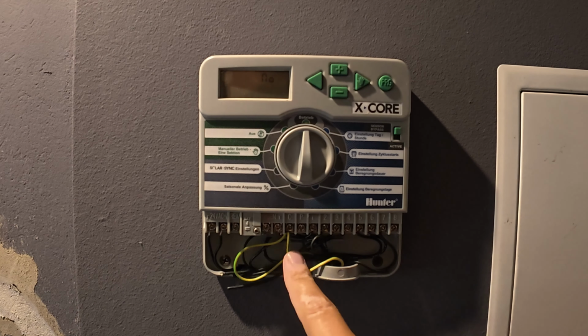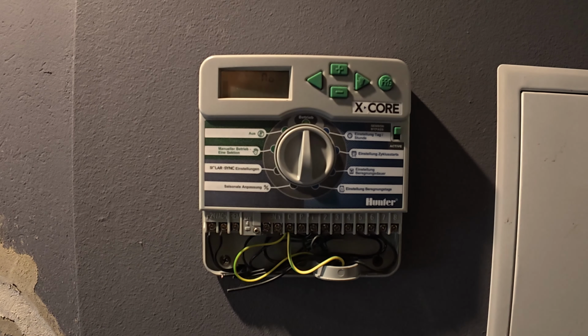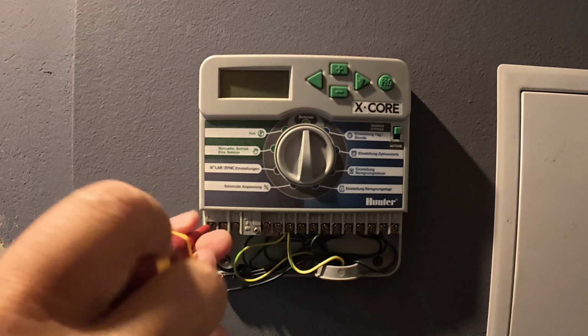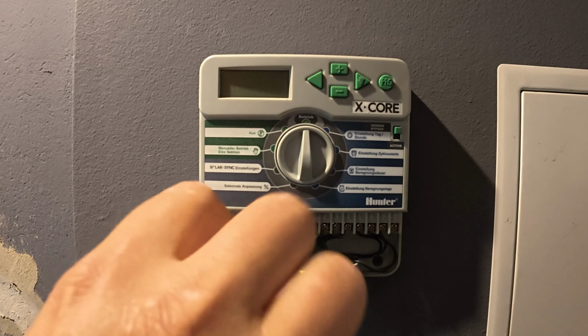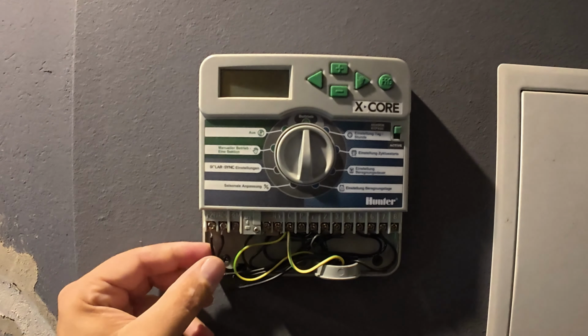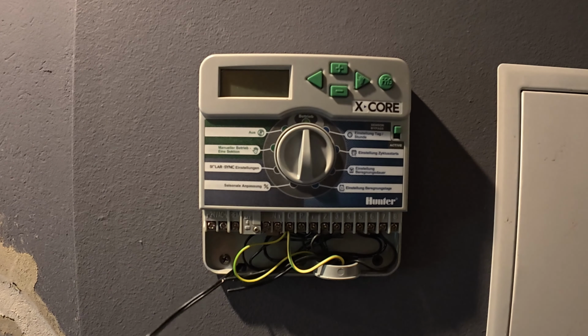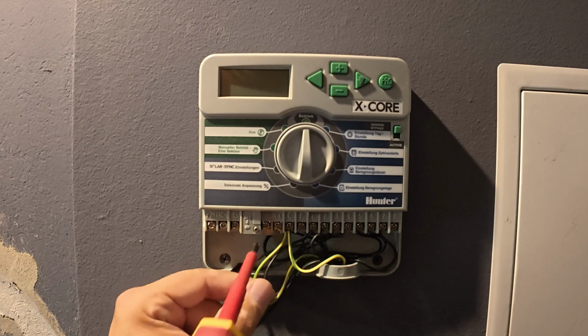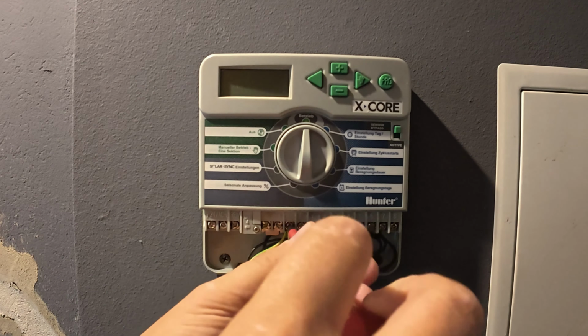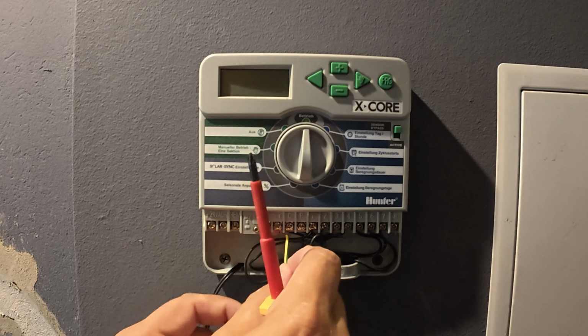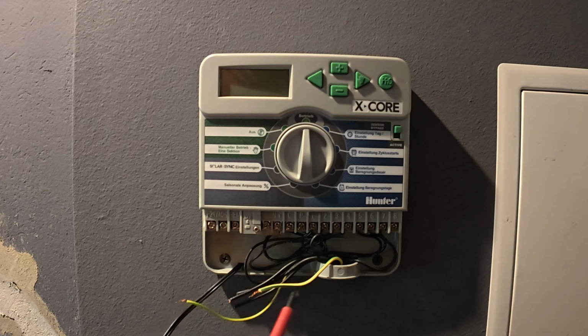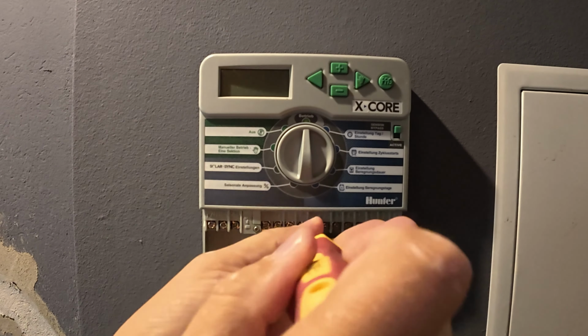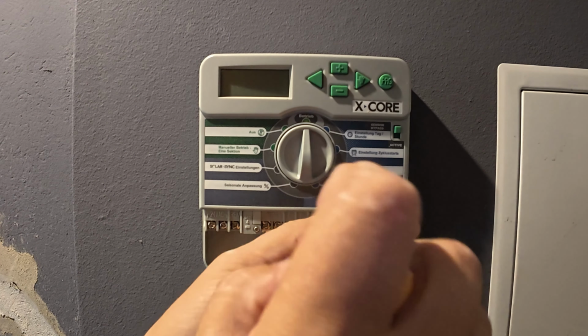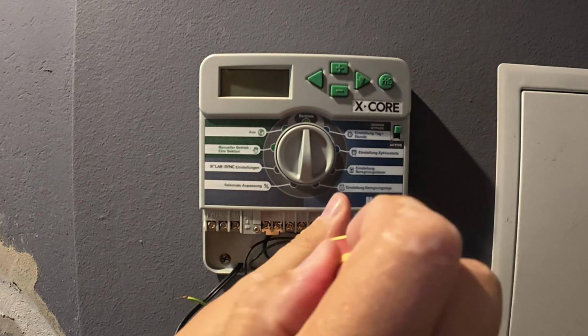Now I can open the terminal connections one by one in order and prepare the cables for the new installation on the Hunter HydraWise. I'll start with the power supply—these are the 2 cables. Then the 2 ground wires, which were securely connected together on the C terminal. Now I proceed to open the screw terminals for the 7 individual valve connections, ensuring each connection point is readily accessible for the next steps in the wiring process.